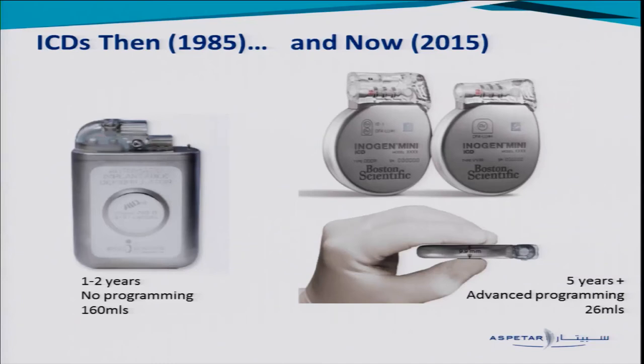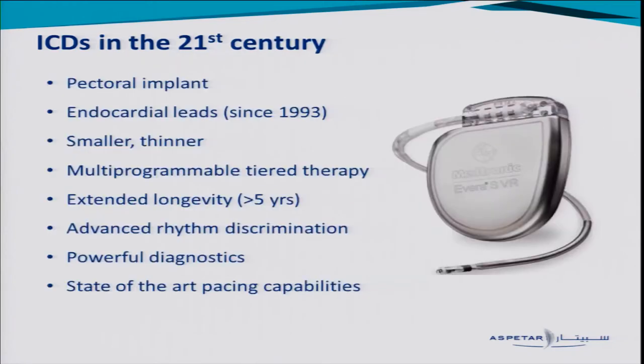The initial ICD had no programming and was 160 mils in volume. ICDs today are much smaller and much more sophisticated. They are all pectoral implants now, unless the device has to go into the abdomen for technical reasons. The leads are endocardial, much smaller and thinner, and the programmability is far more sophisticated. Battery life is much longer — minimum now five years, but sometimes lasting more than ten years. And they have advanced and powerful diagnostics.